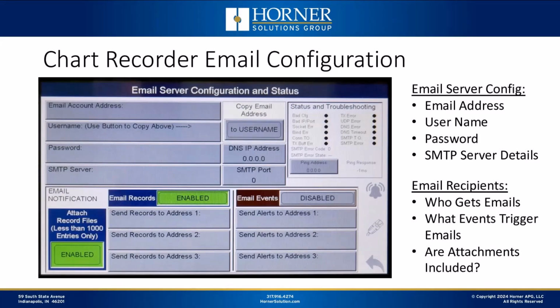In addition to that, if you want to take advantage of alarming via email or maybe delivering log files via attachment on an email, then of course you're going to need to configure email. Configure both the email server, what server is the chart recorder going to get in touch with, or log into when it needs to send an email. And then, of course, you need to have a place where you can type in the email addresses where messages are going to be sent. So that all is handled from the touchscreen here on this particular screen.